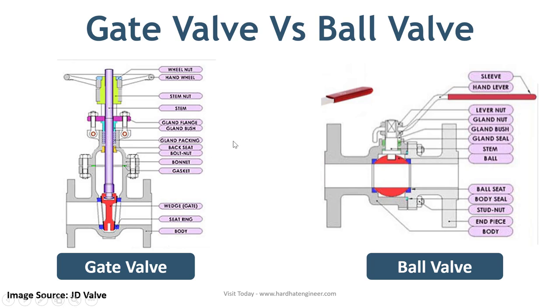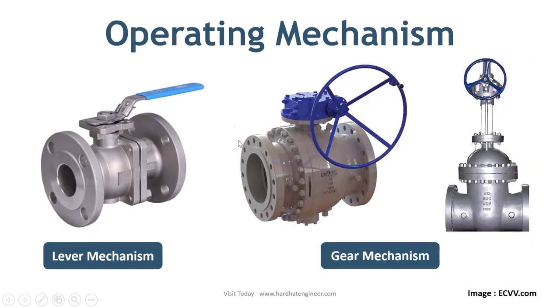Both valves can be operated by a motor or lever. Small and medium-sized ball valves are lever-operated, whereas large-sized ball valves require a gear mechanism with a hand wheel due to the large torque requirement. On the other hand, gate valves are always operated through a hand wheel with or without a gear mechanism, depending on the size of the valve.